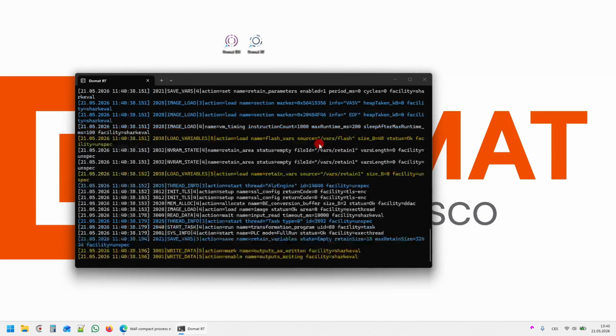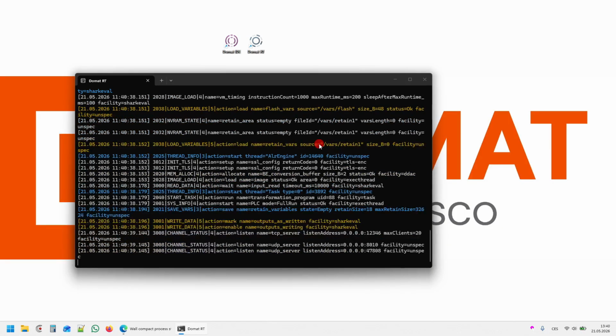It is actually the same process as running in a PLC. So if I want to try the program, but I don't have a PLC at hand, I just need to start the runtime with the icon on the desktop, assign it to the program, and work with it like with a real PLC. I can upload the program and configuration to it. I can start debugging and monitor the values of the variables.